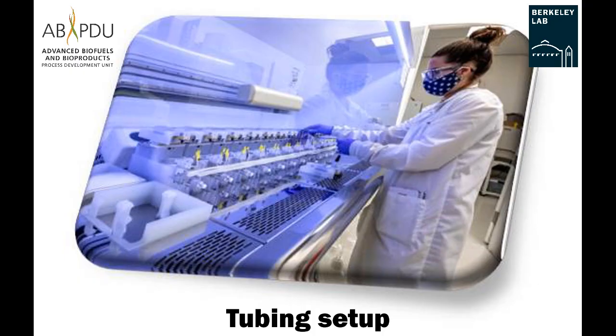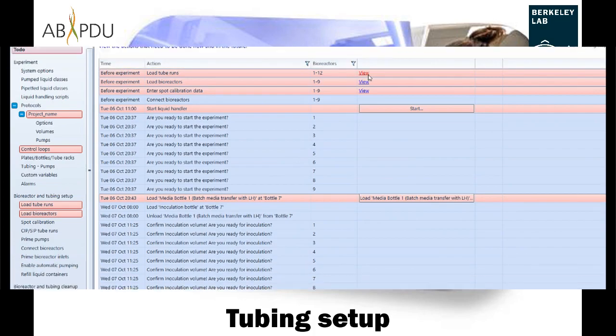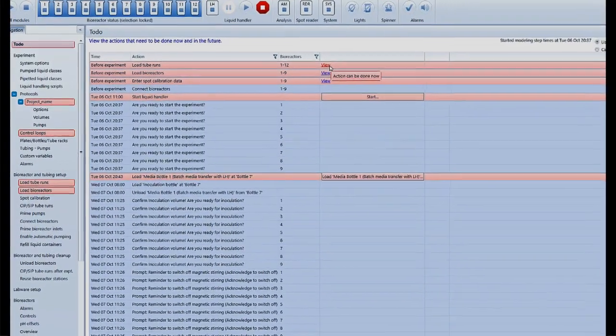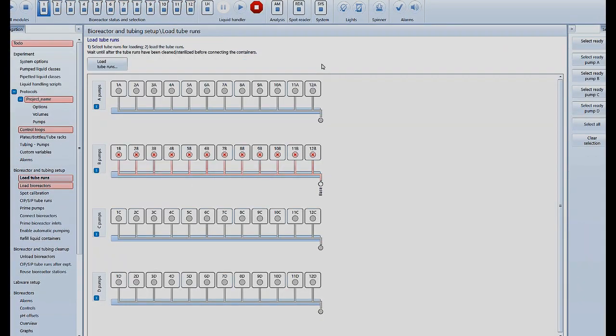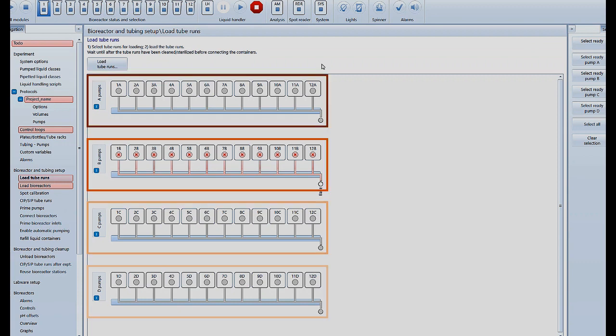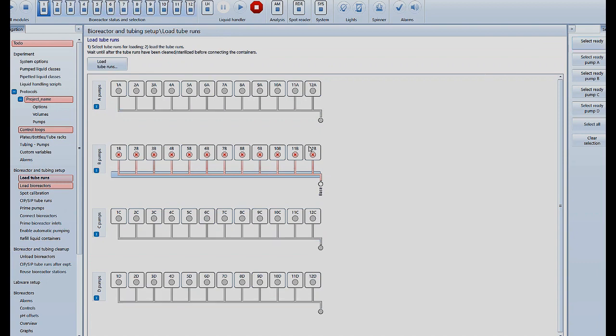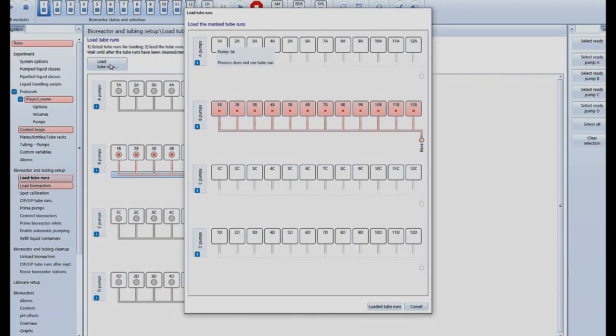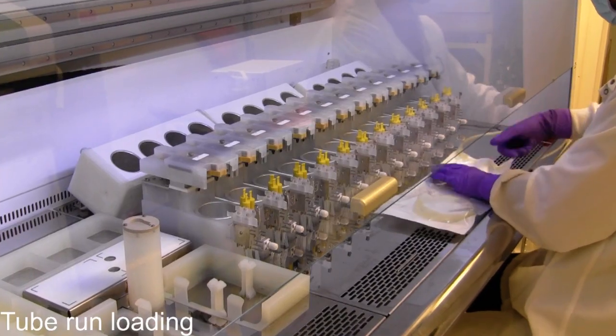Tubing setup. For continuous or semi-continuous liquid additions during the experiments, such as base, acid, or any kind of feed, the Ambr 250 supports up to 4 different liquid sources per experiment in its standard configuration. In this example, we are running a batch fermentation with one-sided pH control, therefore only one tube run is required.